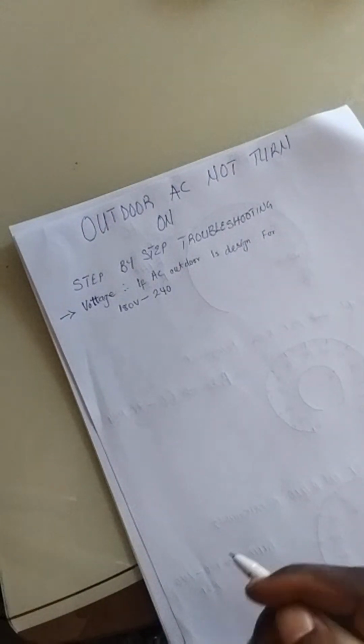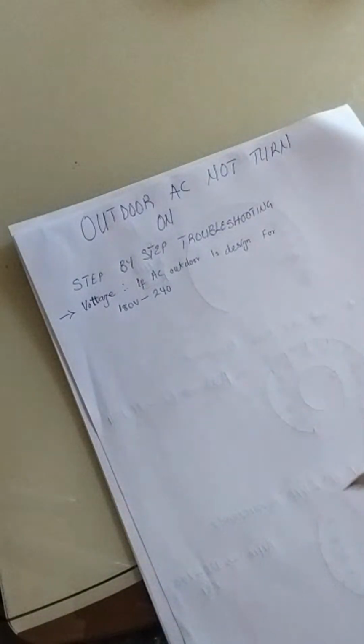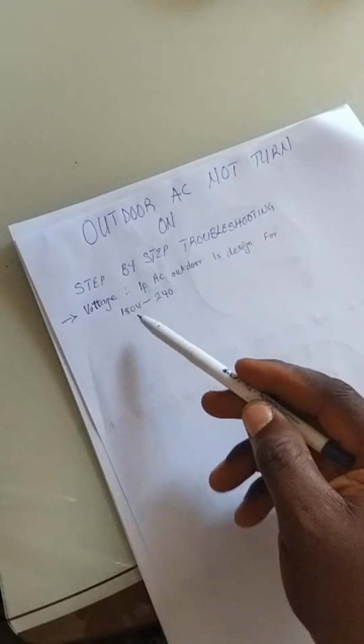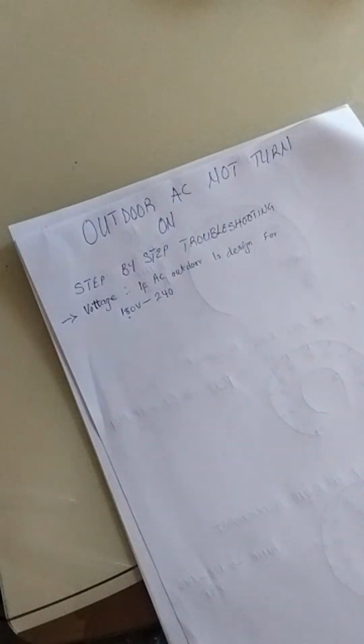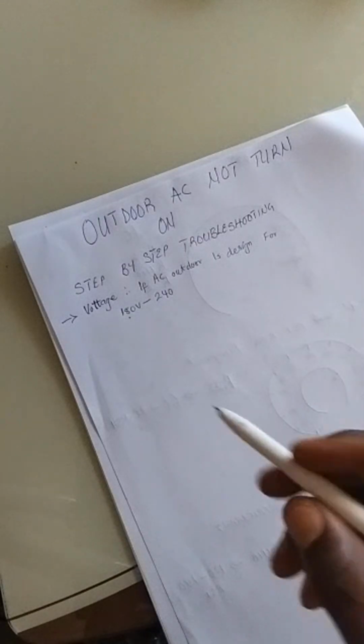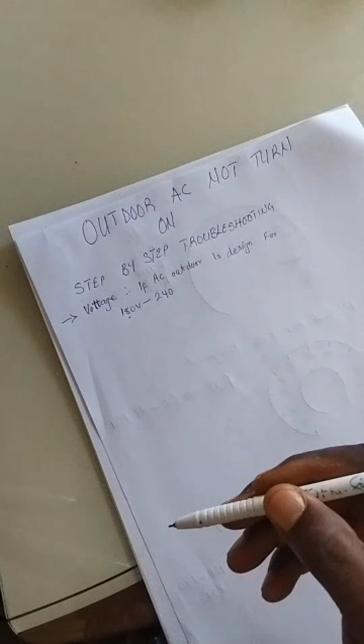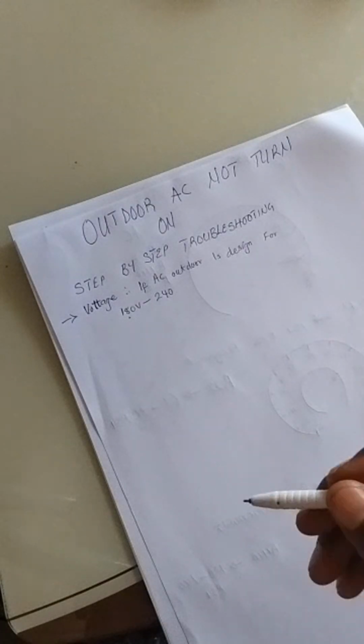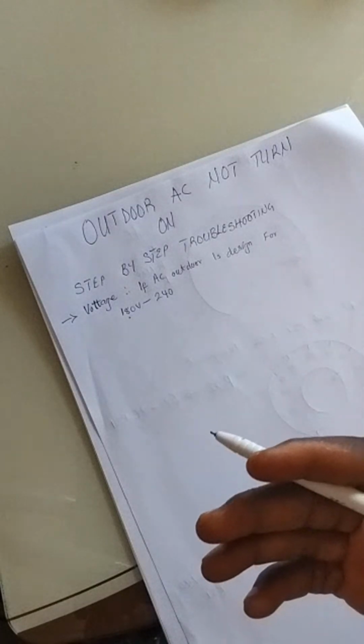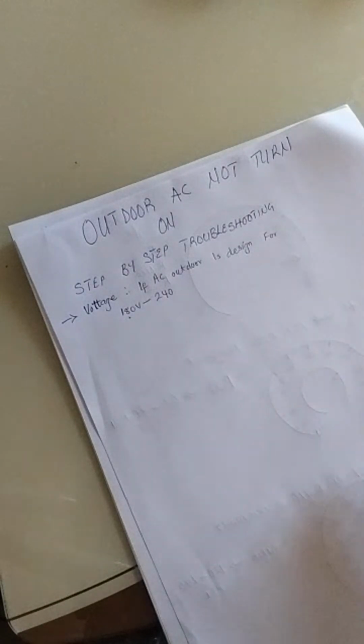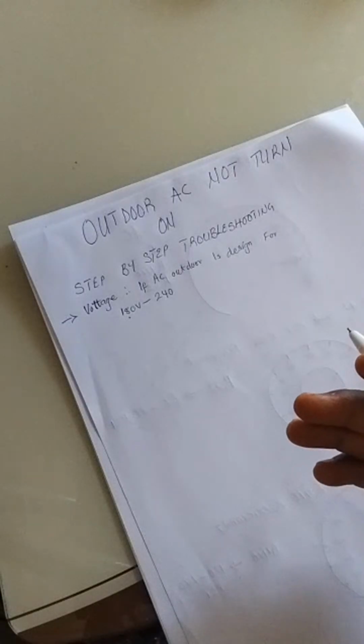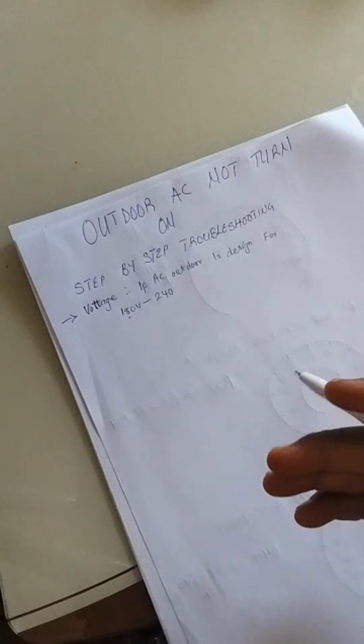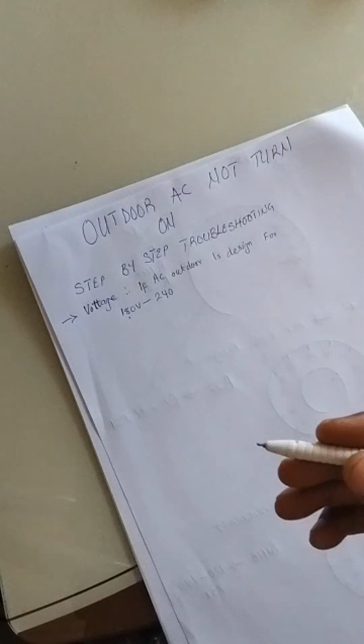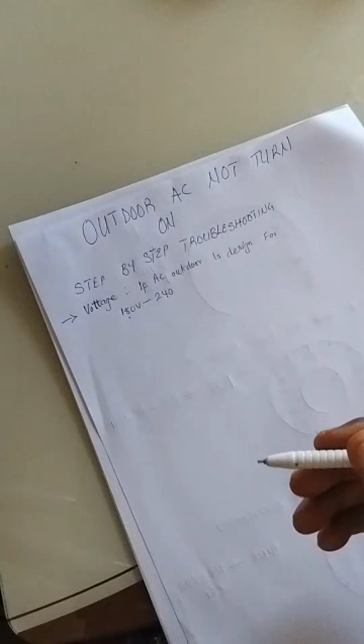It is designed for 180 to 240 volts, and the grid voltage you have in your environment, depending on where you find yourself, if it is less than 180, the outdoor system will not turn on. If your grid voltage is less than 180, your outdoor system will not turn on. The indoor system can turn on and stay on, but if it tries to transfer to the outdoor system through the transfer relay you have on your indoor, it will not turn on. I don't know if you get my point. It will not turn on.